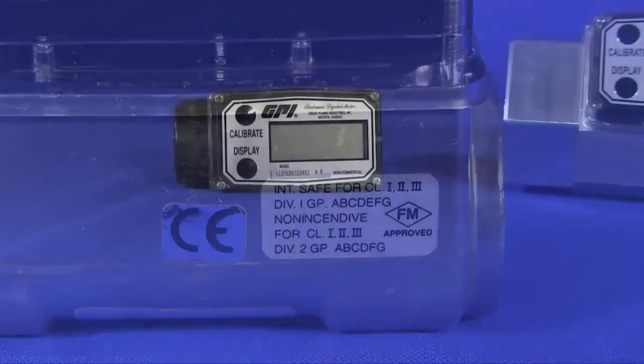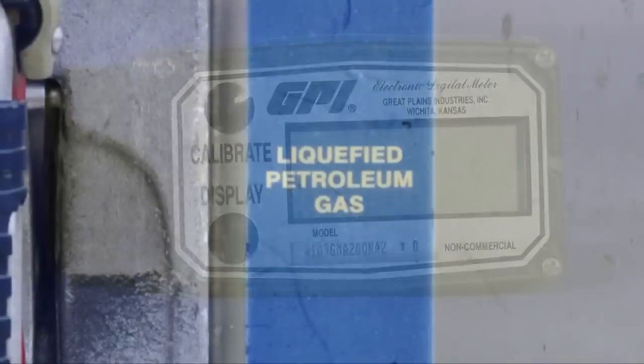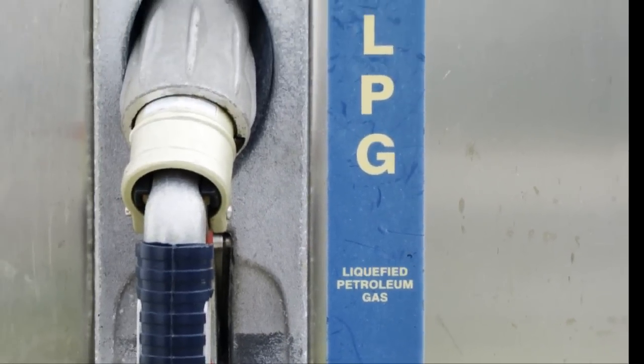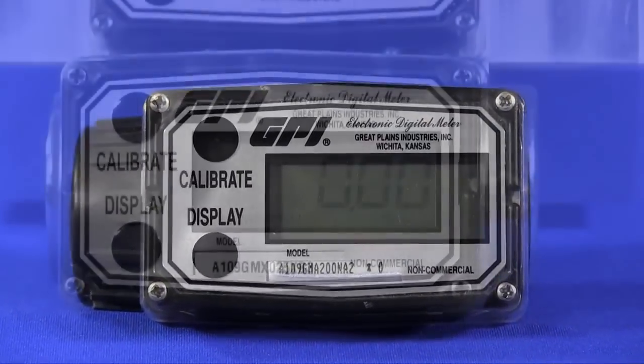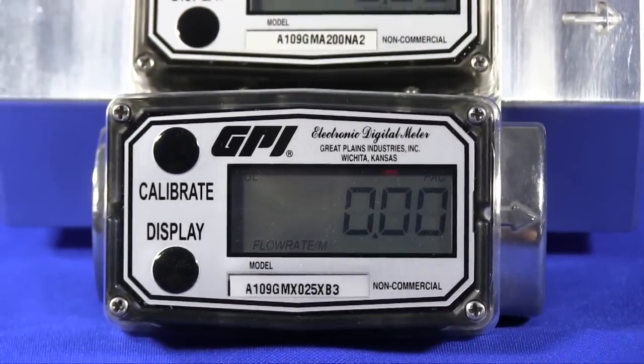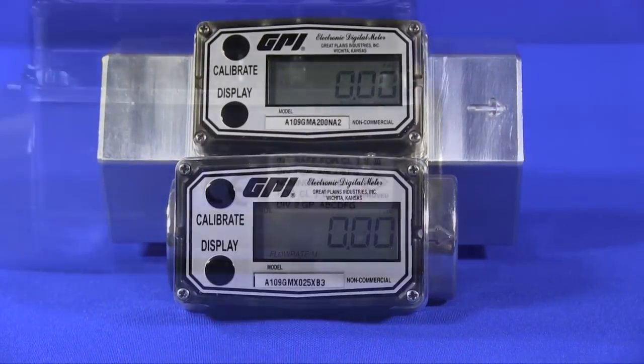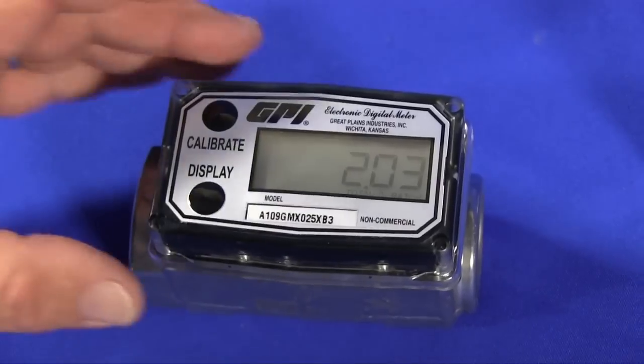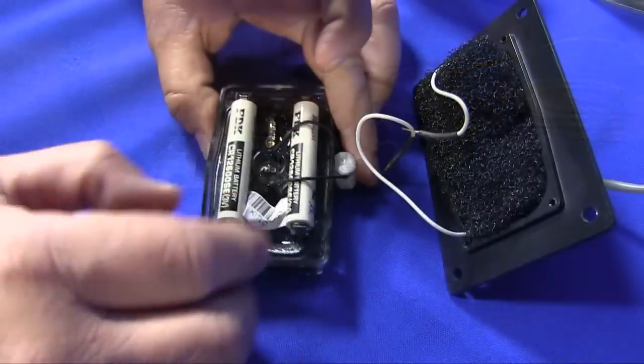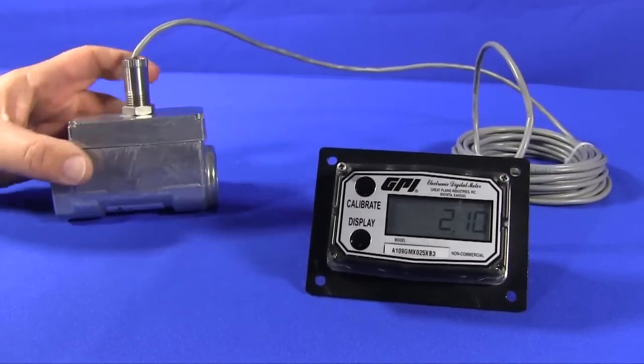With the FM approval, another popular application uses the A1 meter for inventory control and propane and LPG filling operations. The A1 is offered with either a nylon body with 1-inch female NPT connections, or an aluminum body with 1- or 2-inch female NPT connections. Both versions are suitable for hazardous locations and carry a Class 1, Division 1 FM approval. The versatility of the meter can be exploited when you add a remote kit that will allow you to move the display off of the meter body and into a more convenient location with no loss of function or accuracy.